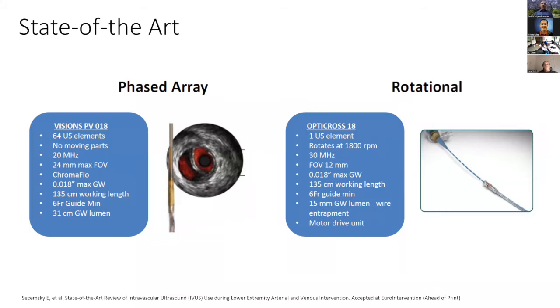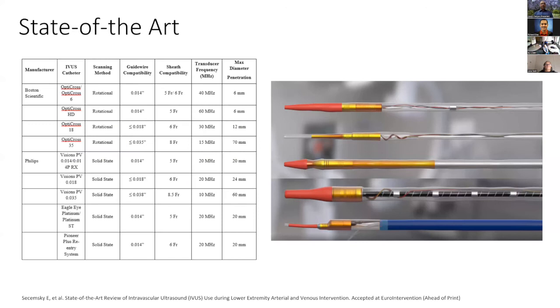Another way that you could achieve the same purpose is having a rotational catheter where the transducer rotates around in a circle and samples the imaging, and then you have to basically put that back together and generate an IVUS image. So Boston Scientific tends to have the rotational methodology. This is coming from a state-of-the-art paper that I mentioned earlier in EuroIntervention. So generally, these catheters are named after the guide wire that they're compatible with. So if you see an 018 catheter, for instance, Visions PV 018 is compatible over the 018 guide wire.